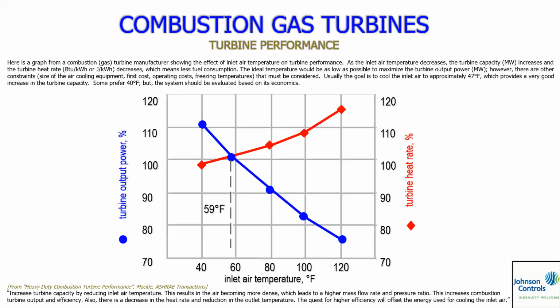All right, so here's a little chart. And I'll just read here at the bottom. This is a quote from Mackey, who's very well known in the ASHRAE circles. Increase turbine capacity by reducing inlet air temperature. This results in the air becoming more dense, which leads to higher mass flow rate and pressure ratio. This increases combustion turbine output and efficiency. Also, there is a decrease in the heat rate. Remember the heat rate, net heat rate, and reduction in the outlet temperature. The quest for higher efficiency will offset the energy used for cooling the inlet air.